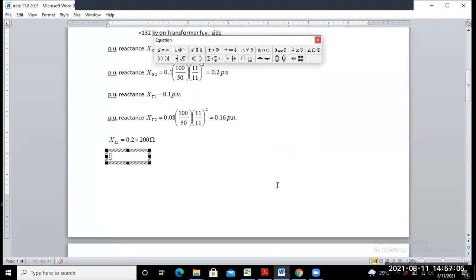Do you remember that one? Base value of impedance is equal to how much? Kilovolt base whole square divided by MVA, is it not? So just put here the value of kilovolt base whole square divided by base MVA. So base MVA is your 100, that does not change.